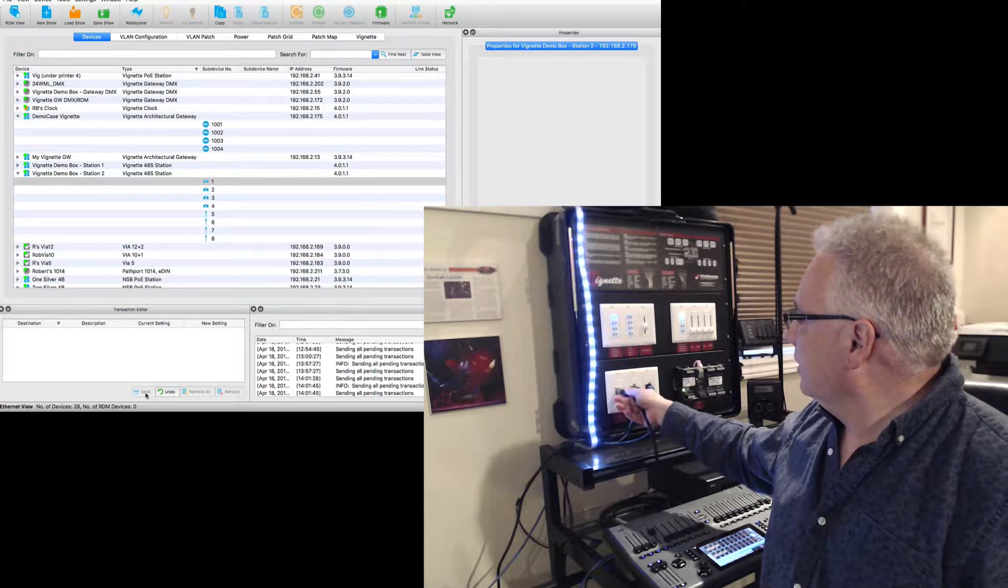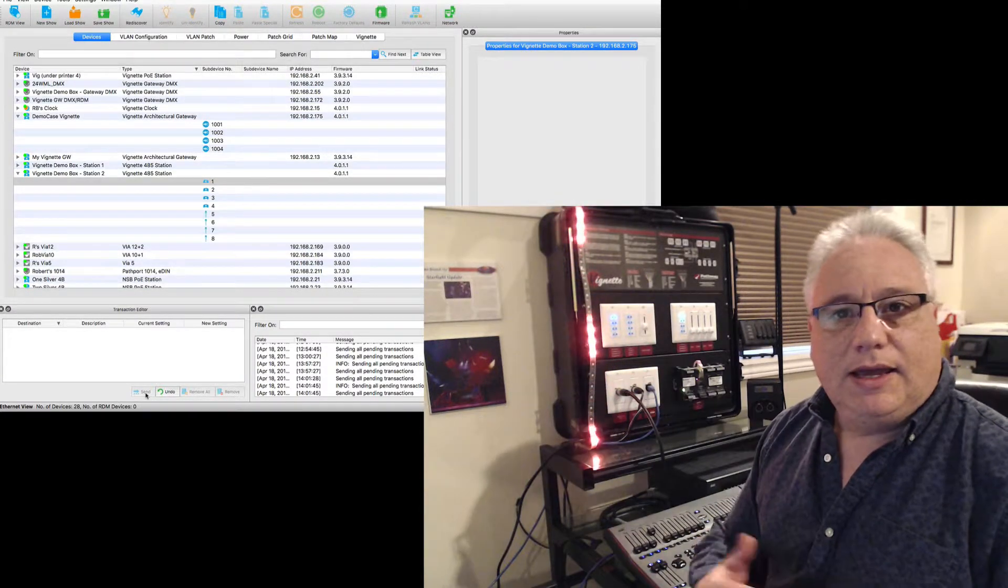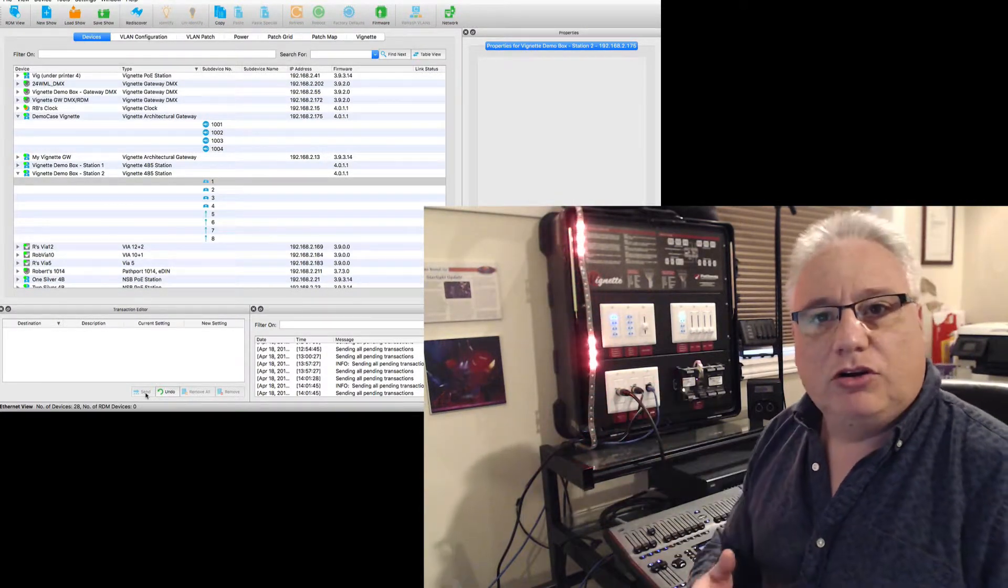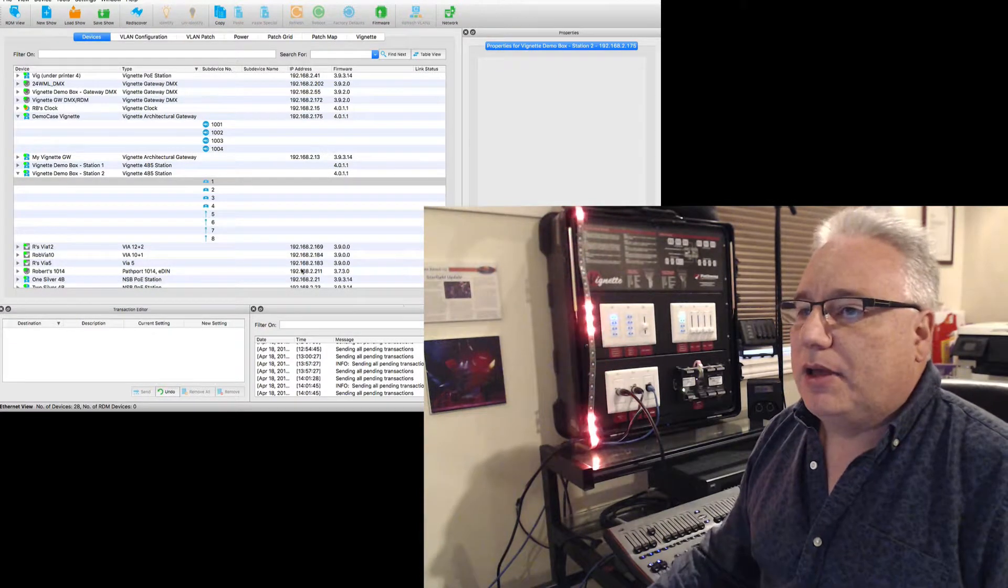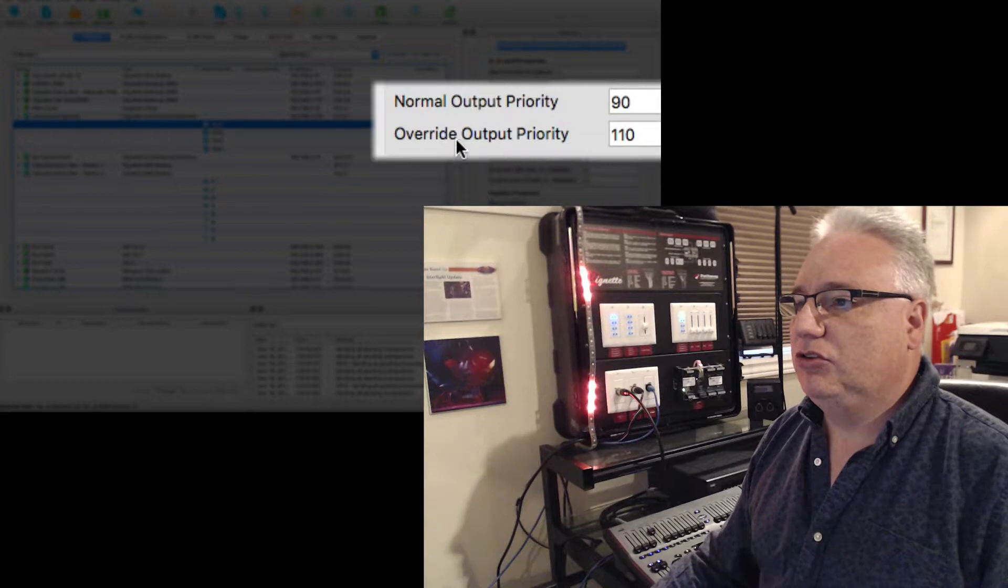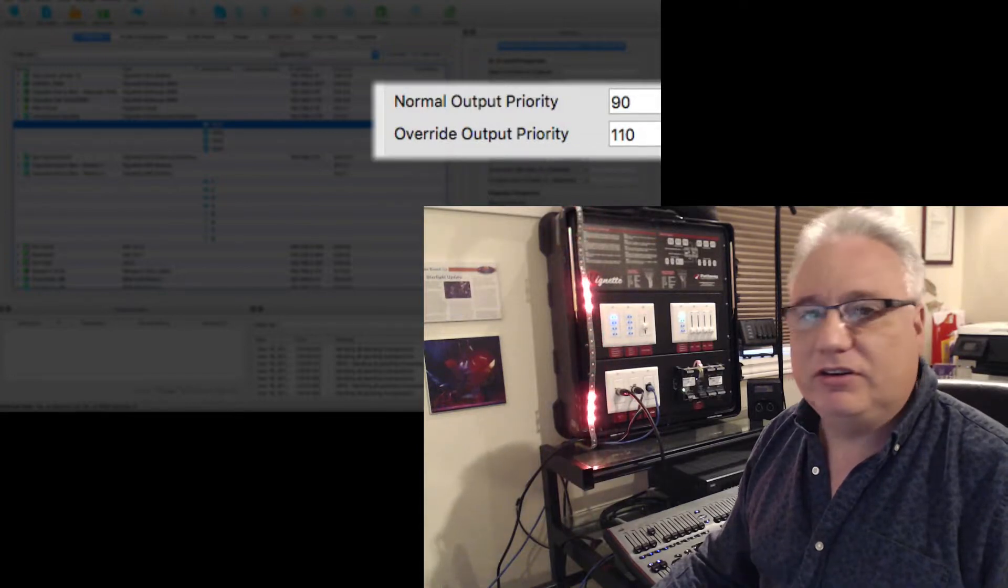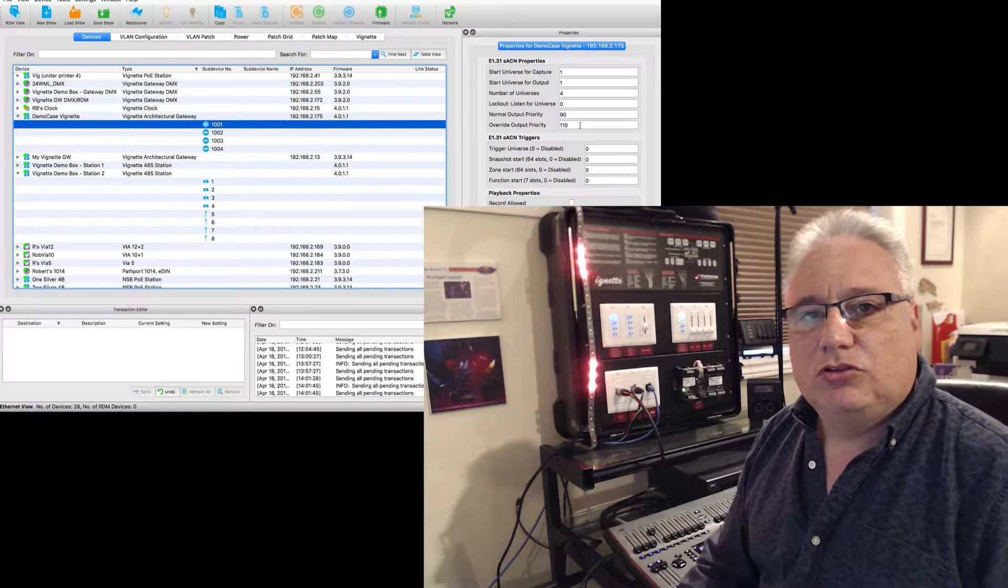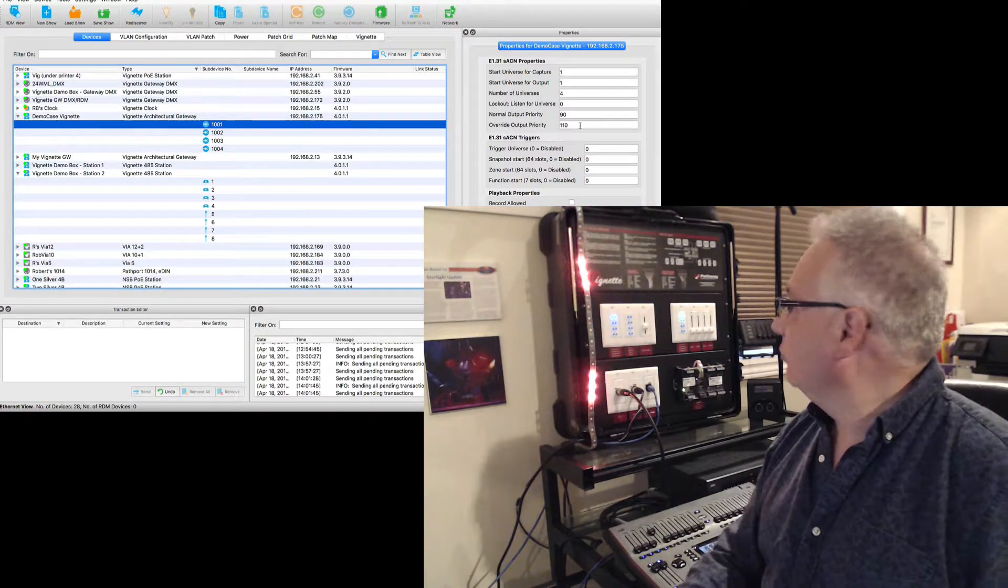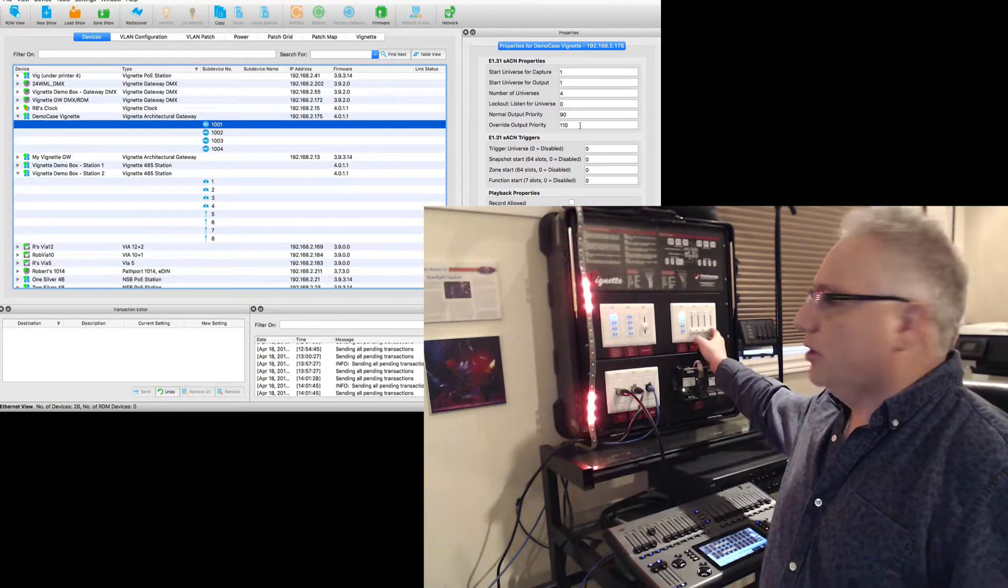If I plug in a lighting console, it comes in because it's configured at priority 100. And if I boost it to output priority of 110, then this system will work.